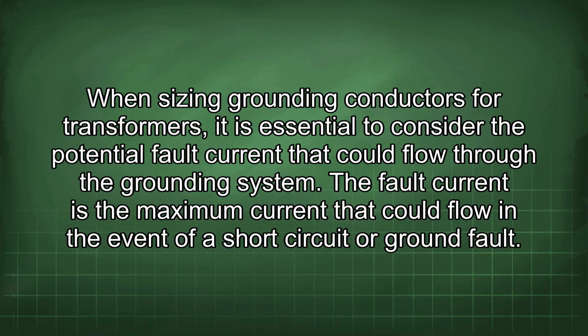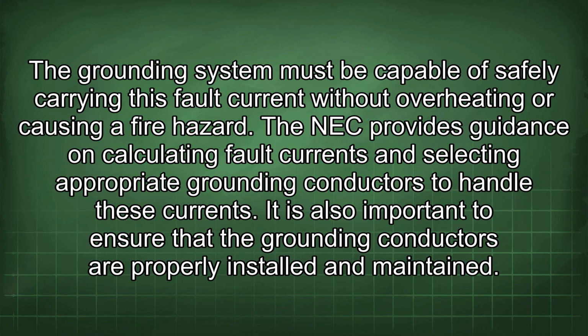When sizing grounding conductors for transformers, it is essential to consider the potential fault current that could flow through the grounding system. The fault current is the maximum current that could flow in the event of a short circuit or ground fault. The grounding system must be capable of safely carrying this fault current without overheating or causing a fire hazard. The NEC provides guidance on calculating fault currents and selecting appropriate grounding conductors to handle these currents.